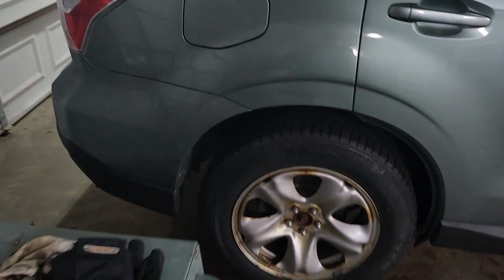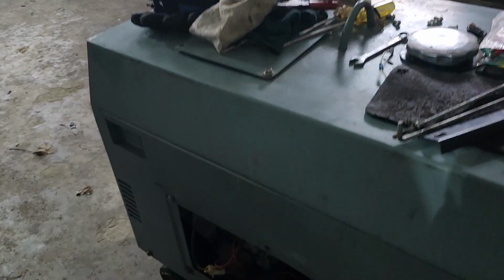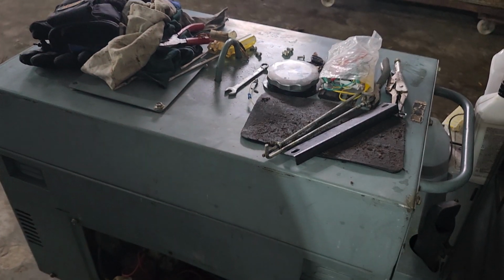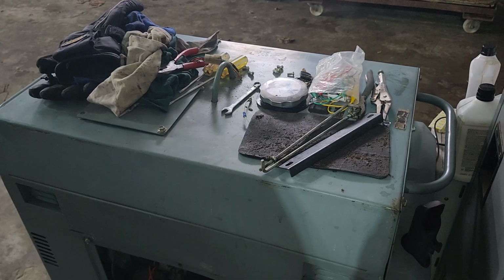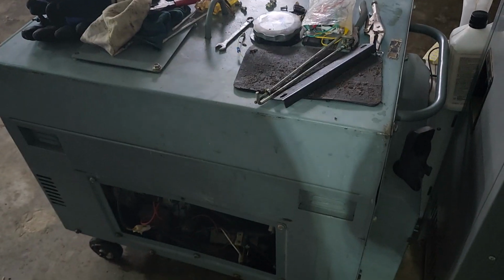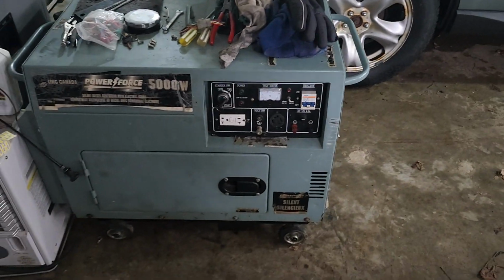Then I ran into another issue. This machine has a failed controller. That's the white box down there. Everything's now been disconnected because it kind of let out the magic smoke. Nothing came out on the generator side or anything important on here. Just the control electronics let out the magic smoke. The box was not working properly to begin with. So this machine would not self-start.